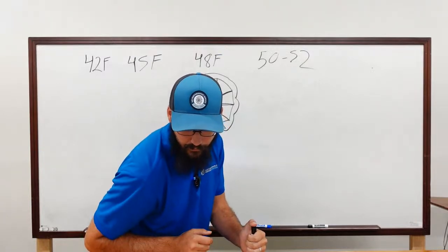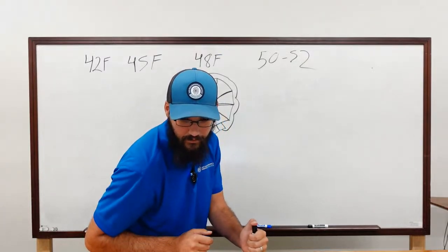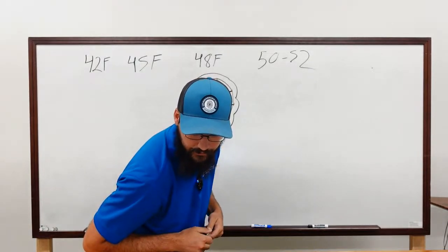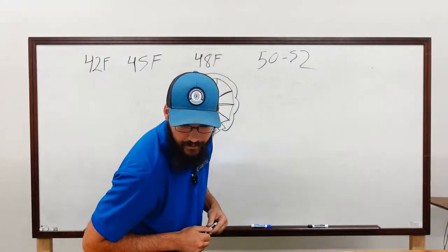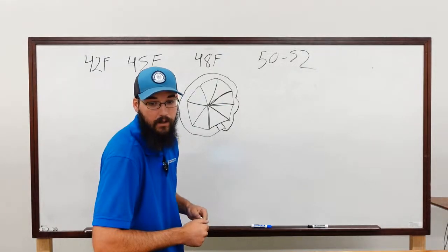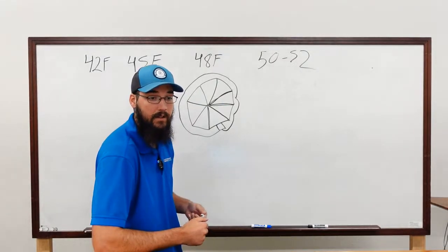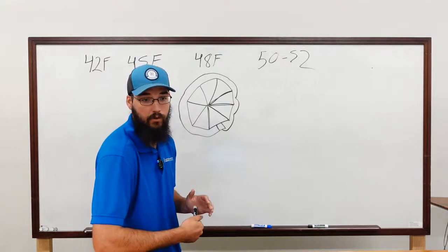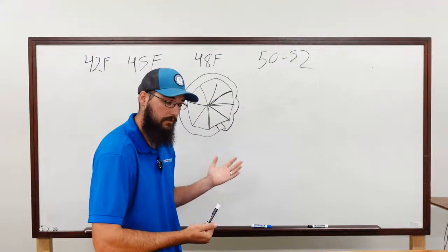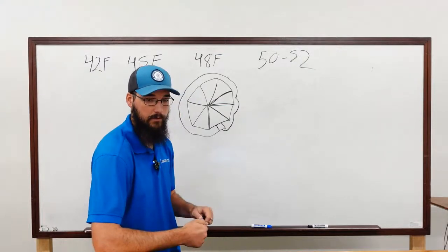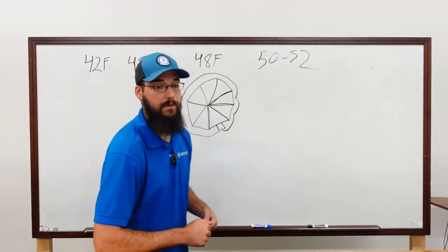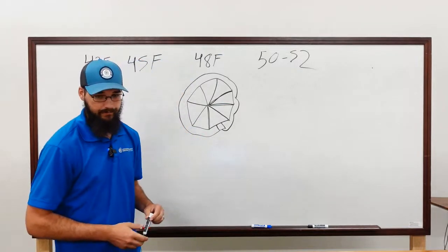Is it okay to cycle the screw off and on for that? Please go slightly deeper on that question there, Jeff. You should have a minimum GPM to stage both at lower capacity if available, right? Yes, and when you say minimum GPM, that's saying that you have a variable flow system to begin with. Personally, I'm not a huge fan of variable flows, but they exist, they work, they're part of our system. But yes, you need to make sure that you're paying attention to the GPM guidelines set per that chiller.